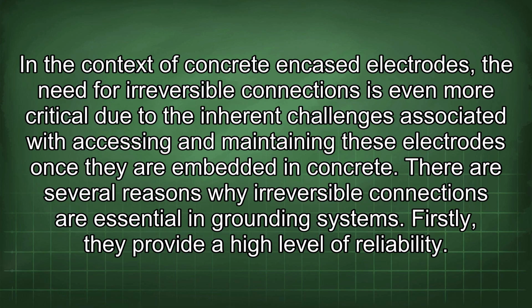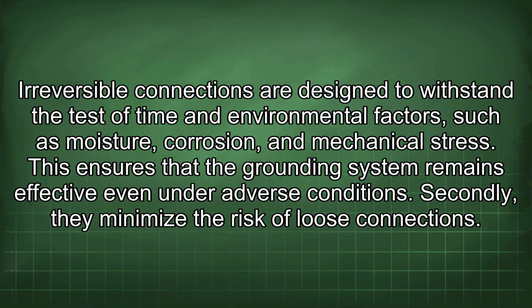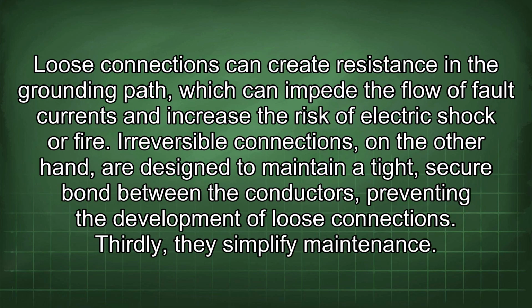There are several reasons why irreversible connections are essential in grounding systems. Firstly, they provide a high level of reliability. Irreversible connections are designed to withstand the test of time and environmental factors, such as moisture, corrosion, and mechanical stress. This ensures that the grounding system remains effective even under adverse conditions. Secondly, they minimize the risk of loose connections. Loose connections can create resistance in the grounding path, which can impede the flow of fault currents and increase the risk of electric shock or fire. Irreversible connections, on the other hand, are designed to maintain a tight, secure bond between the conductors, preventing the development of loose connections. Thirdly, they simplify maintenance.